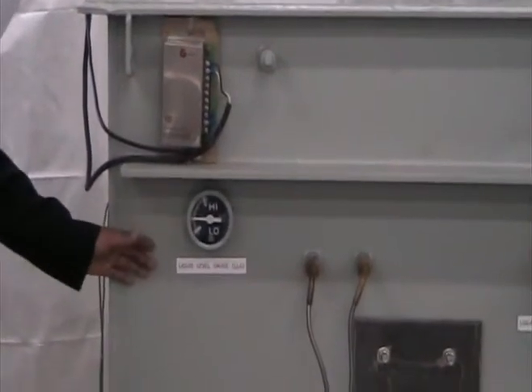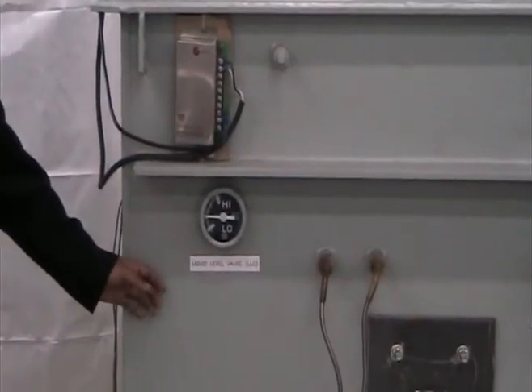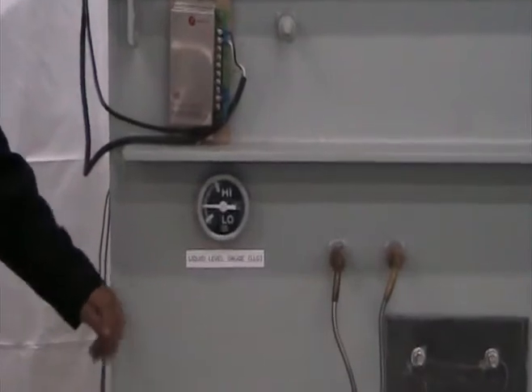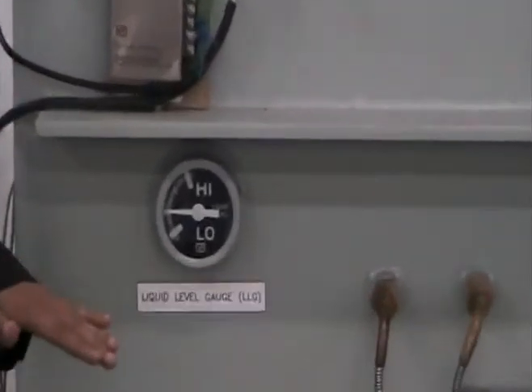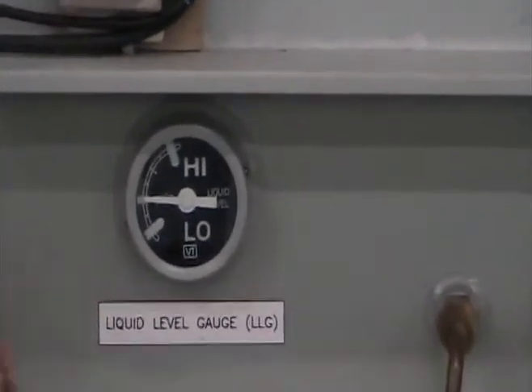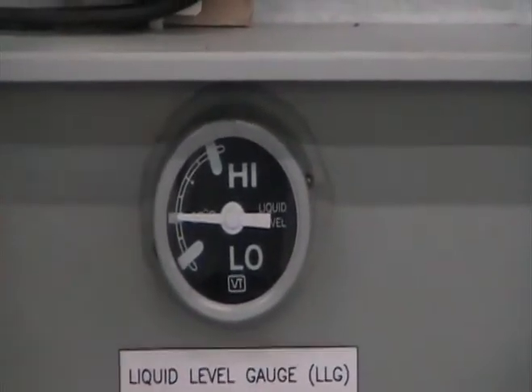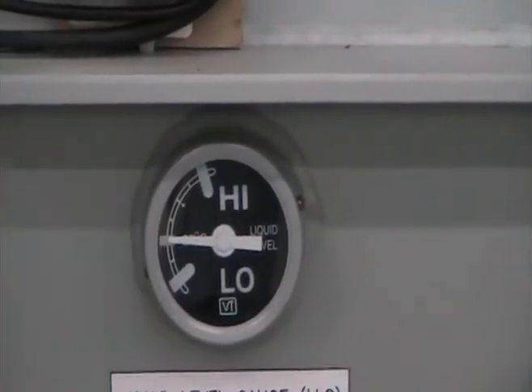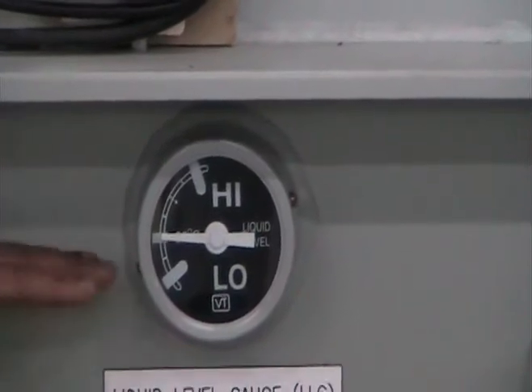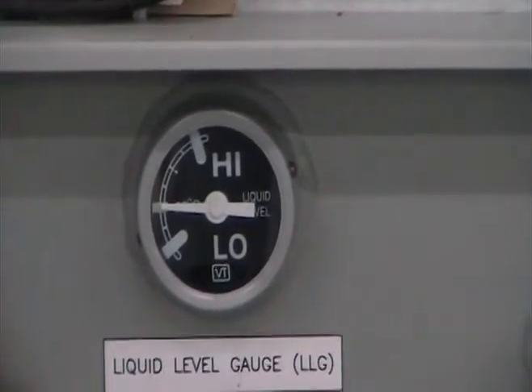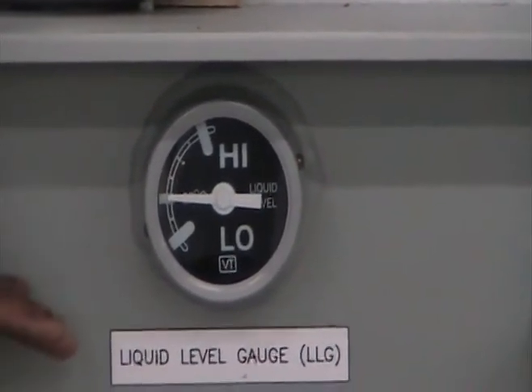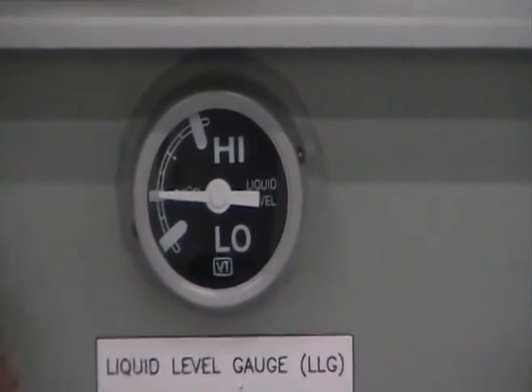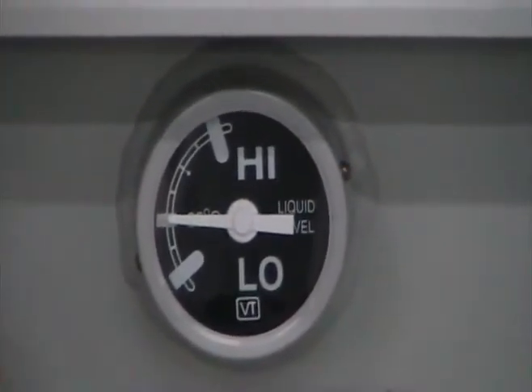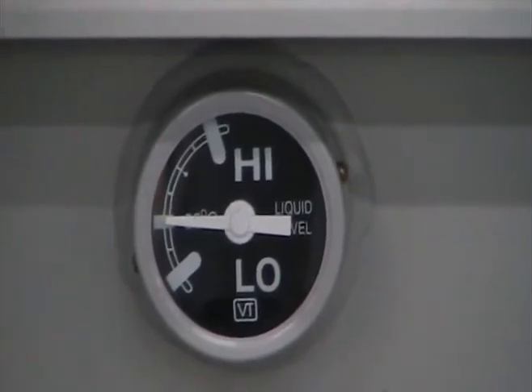Now I will demonstrate how the VCM2 monitors the transformer's liquid level. We will compare the 25 degrees centigrade liquid level reading on the VCM2 screen with the reading of the liquid level gauge. With the conventional system, the analog gauge shows the low level, high level and 25 degrees centigrade level. Also, the alarm contacts are activated when it exceeds the low level or high level. This is the only information available on the gauge.